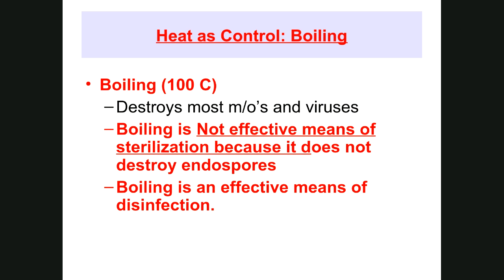Okay, so boiling water, 100 degrees centigrade, is not an effective means of sterilization because it does not destroy endospores. It is, however, an effective means of disinfection. And not just endospores, there are some bacteria capable of surviving being boiled at 100 degrees for 30 minutes. So again, it's not effective at sterilization, but it is very effective at disinfection.